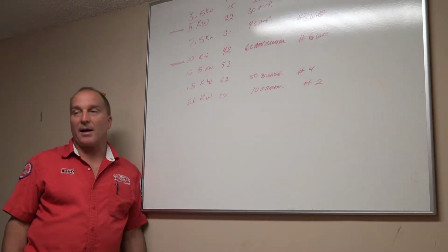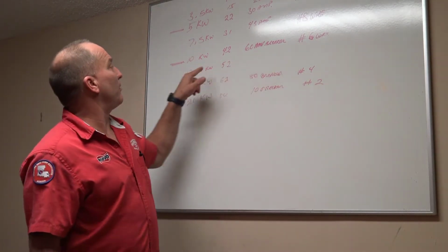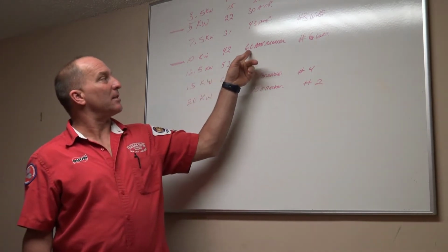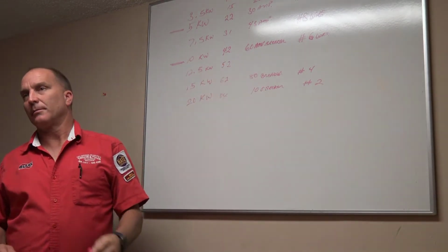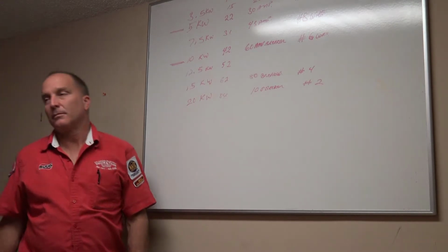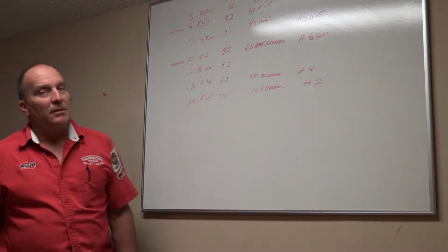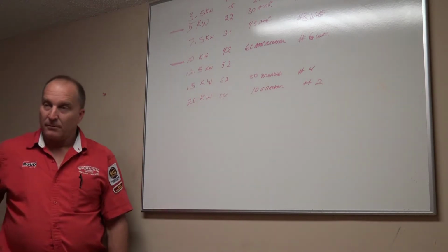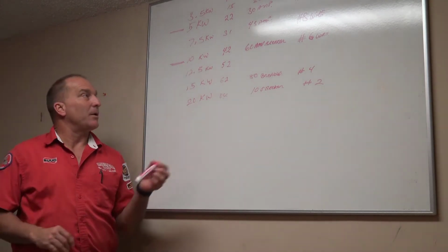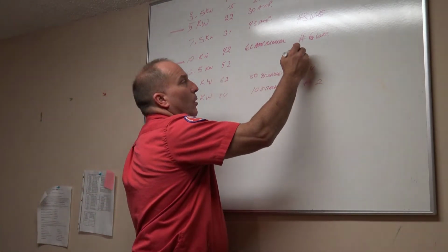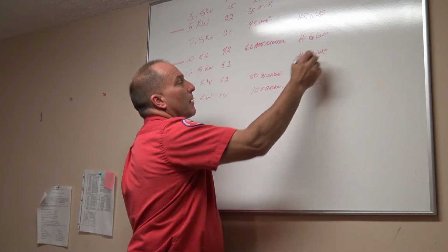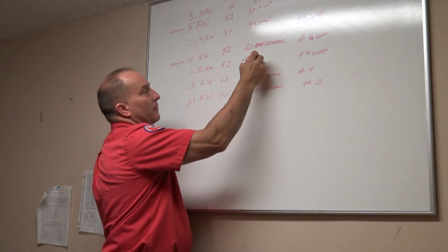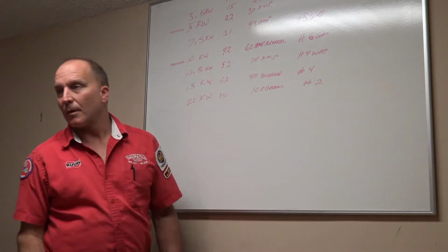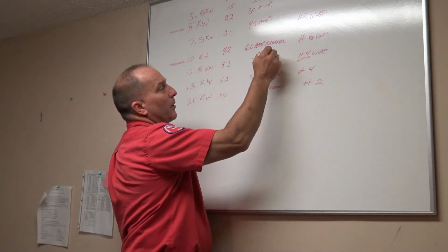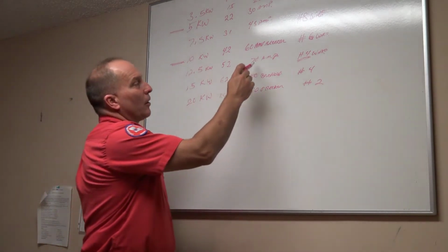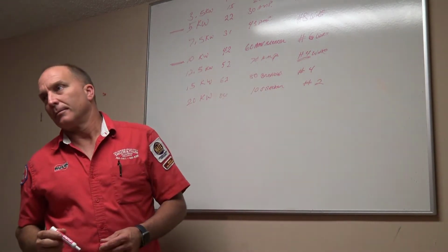If I'm running one wire size to it, am I going to bring a number 6 wire on 12.5 kW? It's 52 amps. It's holding a 60 amp breaker. Will it hold it? Yes, it would hold it. Is it too tight? Yeah, it's too tight. So if I'm going to do that, I'm still going to run a number 4 wire, but I might put a 70 amp breaker. Okay? Because with your wire size, you don't want to burn, guys. It's okay if I put a lower amp breaker on a higher wire. Okay?